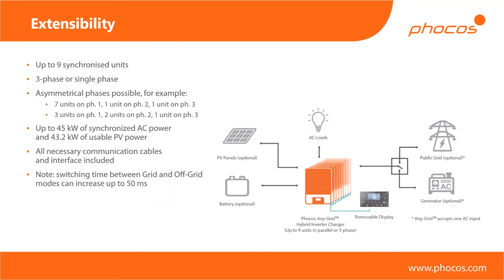I'd like to look at extensibility as the last topic that's, let's say, a little bit less technical than the final 2 topics. For extensibility, you can see as a recap here your typical system, how it would look with the various optional components in your system. Now, if we want to have more power than what one AnyGrid can deliver, regardless of whether it's a 3 kilowatt or a 5 kilowatt model, we can hook up to 9 of these together. And we're very free in how we hook them together. We can have all units on a single phase. So we can have a single phase system with 45 kilowatts of synchronized AC power on a single phase.